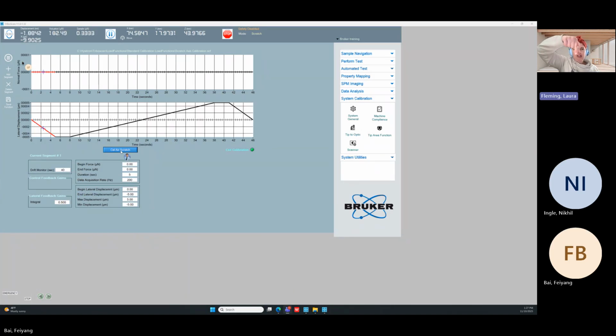Instead, if we walk through this calibration, it moves back 5. That's that first leg where it goes in lateral displacement from 0 to negative 5. Then it holds, and then it goes from negative 5 to positive 5, holds, and then it comes back to 0. So 0 to negative 5, negative 5 to positive 5, so a 10 micron scratch here. Hold, and then back to 0. So during this long scratch, we know that the force felt should be 0. We're in the air. We're not scratching against anything. Just like in the normal indentation axis calibration, it's going to take that data, the spring data, know that it should be 0, and correct the electrostatic force to make that true.